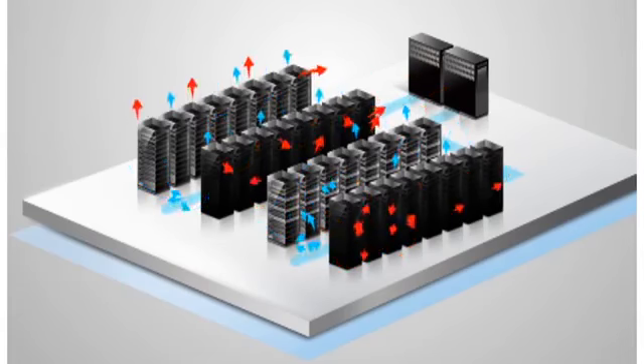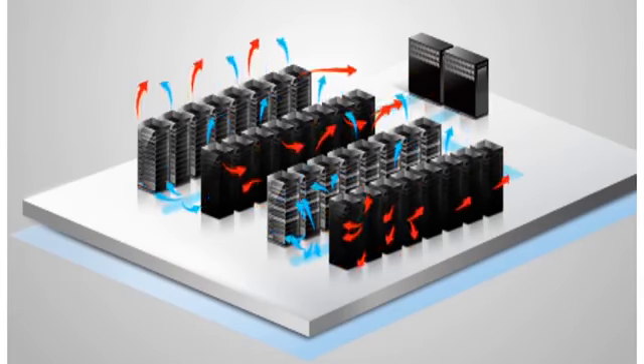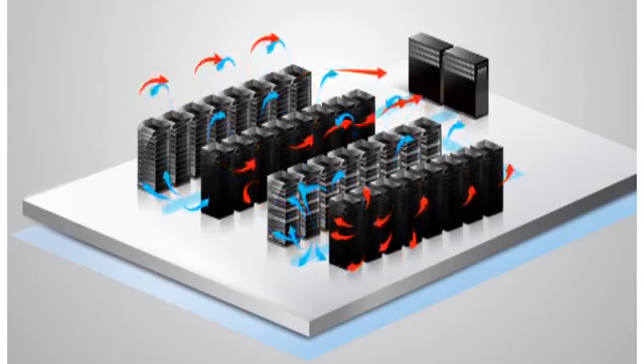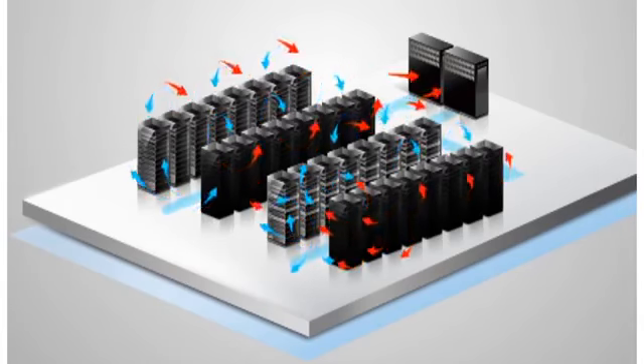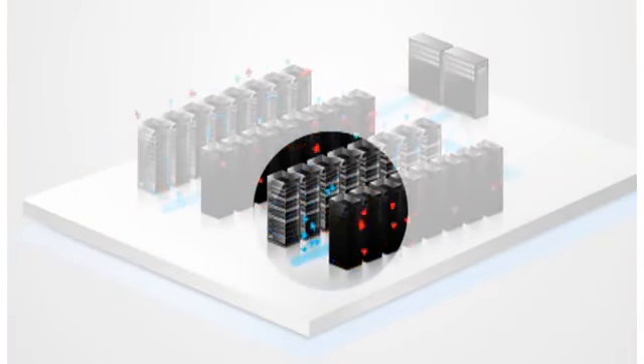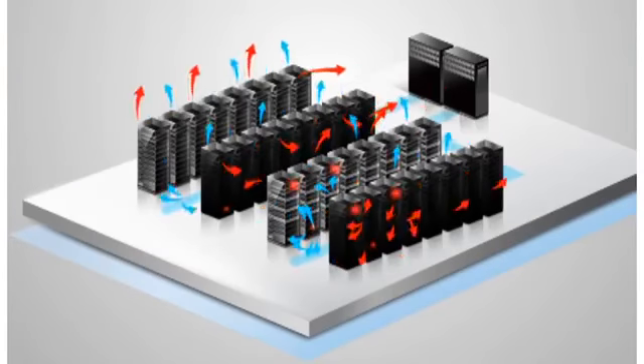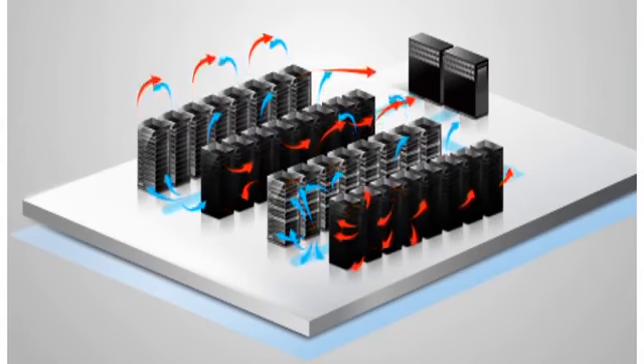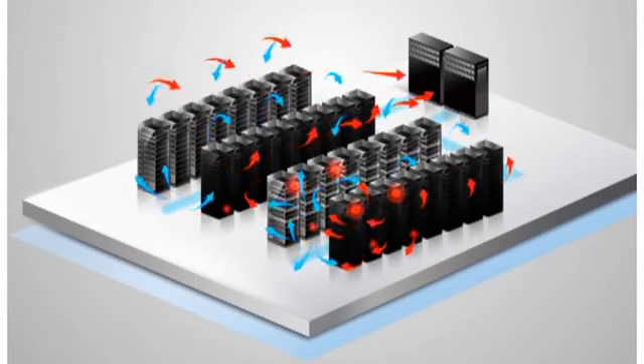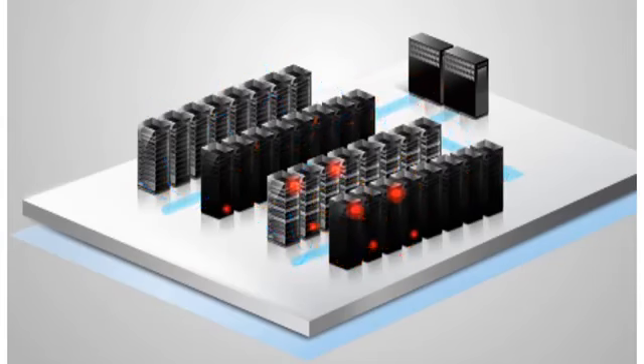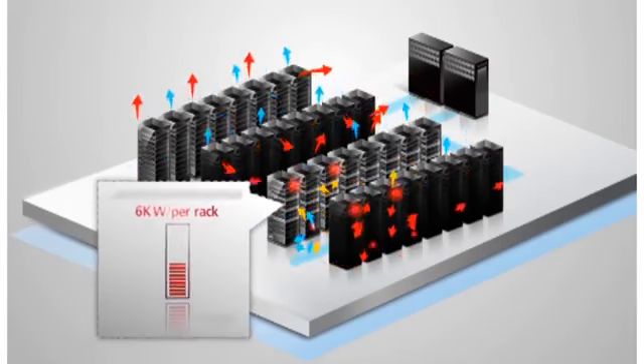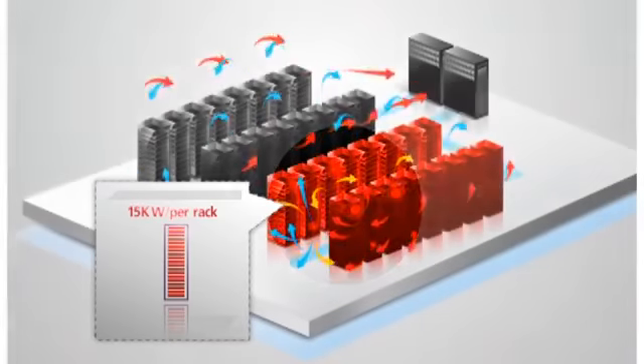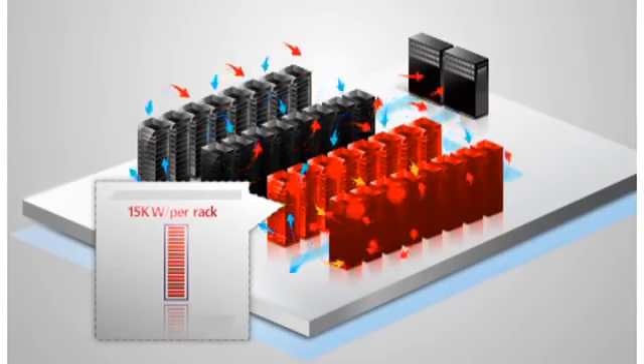In this method, spaces in a data center with high-density server racks contain the following negative conditions. A. Airflow can't be controlled. B. Hotspots grow. C. Air conditioning systems continuously compensate for airflow that cannot pass through server cabinets. D. Cooling capacity per rack is below 6 kilowatts per rack.